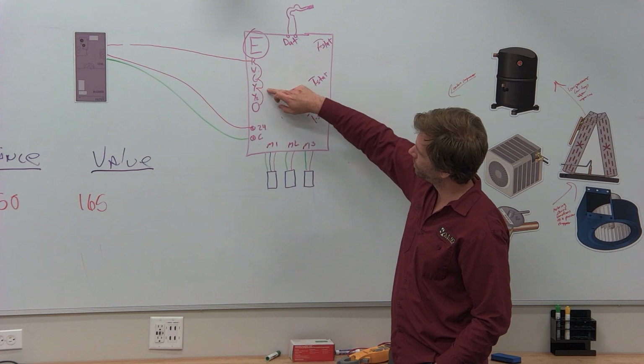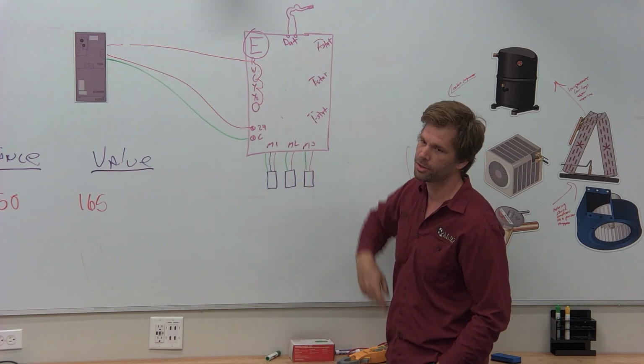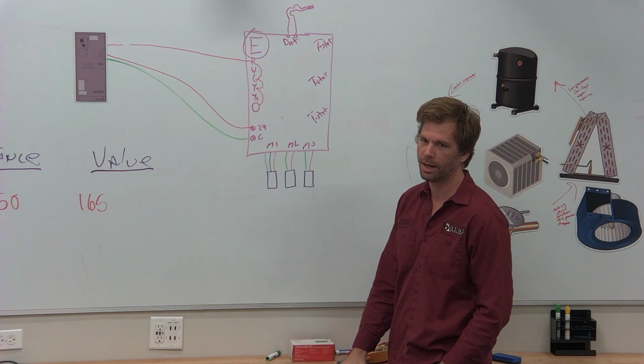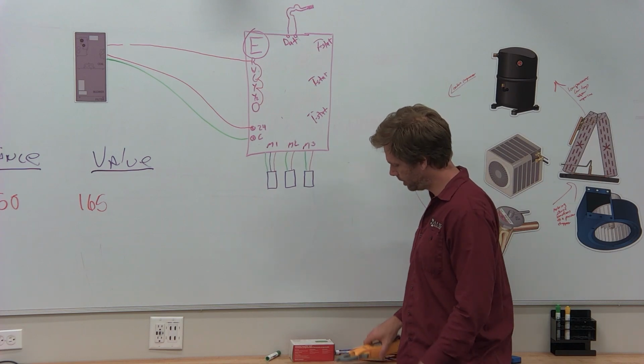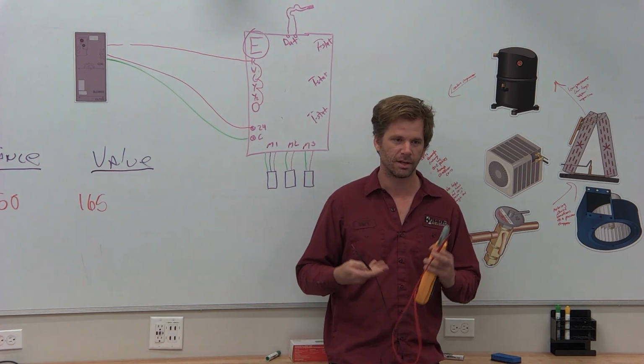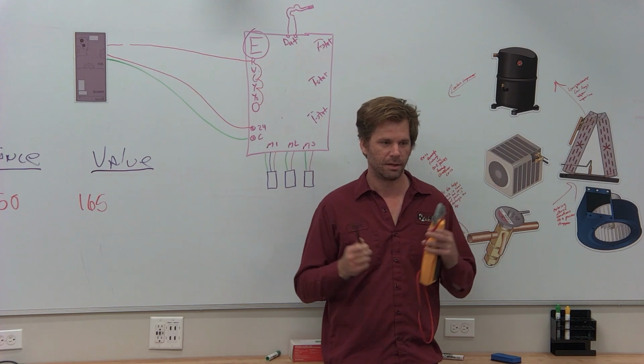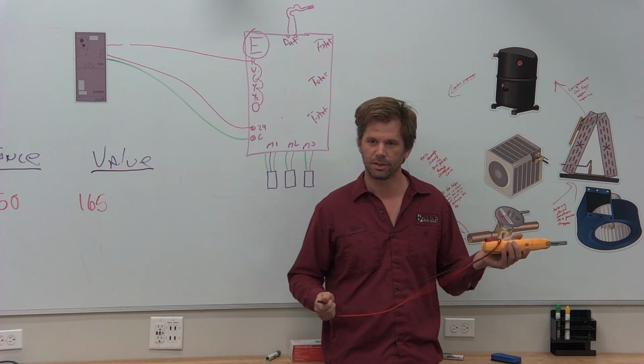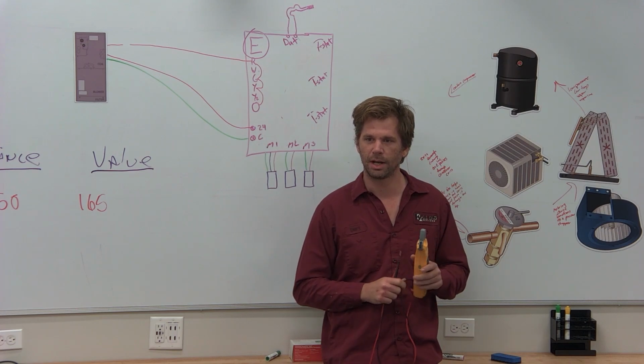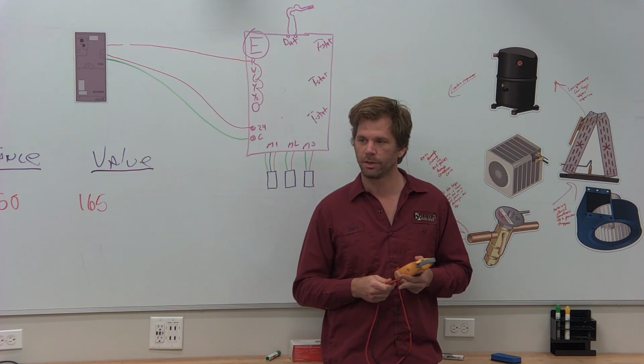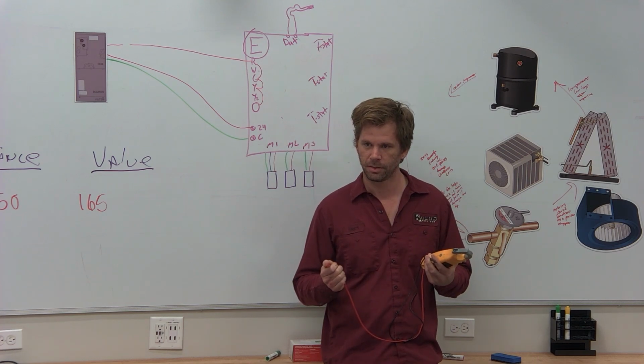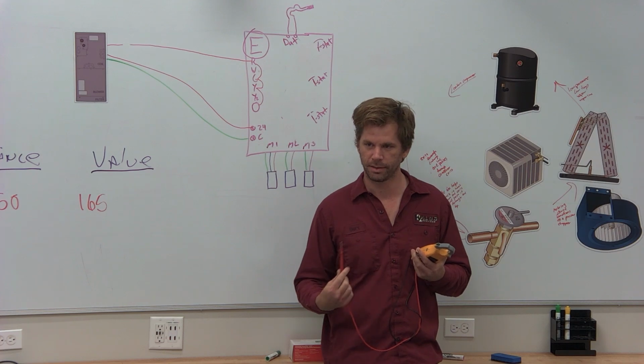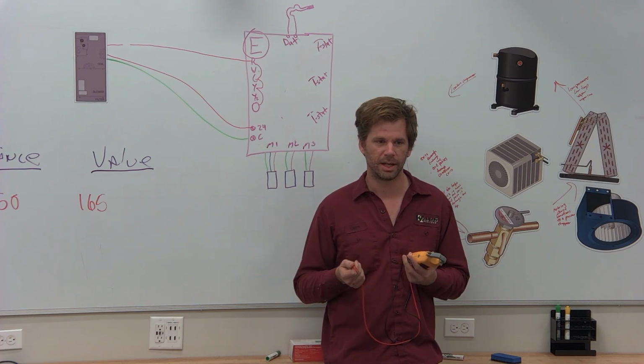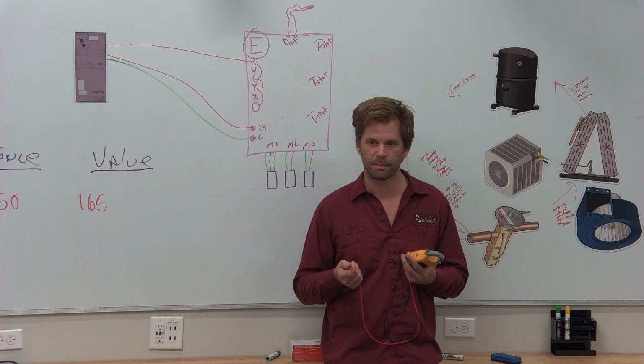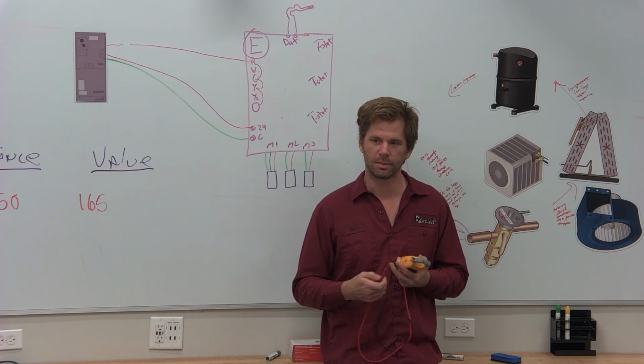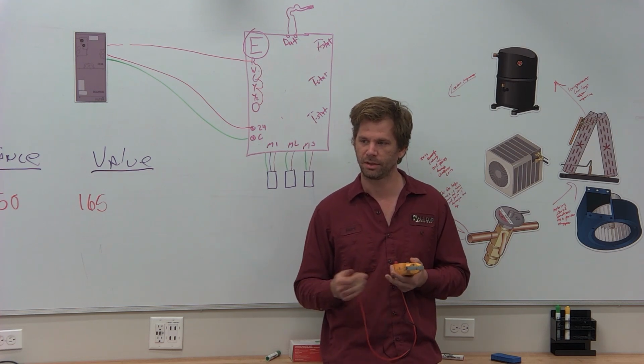If you have 24 volts on Y, then you check between R and Y and your meter shows you 0. That means you have 24 volts on Y, because your meter will show you the potential difference between these 2 points. It measures electrical difference. If both wires have the same 24 volts on them, it'll show you 0. This is another reason why when we go to check safety on a condenser, we don't check from leg to leg before we touch it. We check from leg to ground, right? Because we're ground. And there may be 0 volts from leg to leg because they both are energized with the same line of power. But we're ground and we're about to touch it, there's a potential difference between us and that wire. So we check to ground before we touch things.